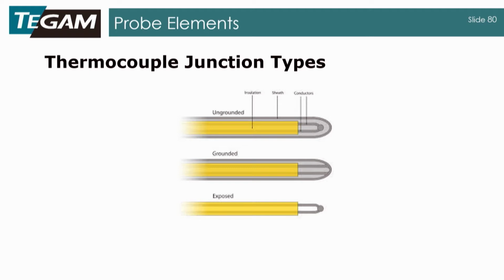Next is the grounded type. It's pretty much the same setup, except right here you can see that your thermocouple junction is actually bonded to the sheath. And then lastly, you have an exposed. And this is usually used for an air or gas measurement, and the obvious difference here is that there is no sheath, and you're just relying on the insulation and the thermocouple junction. This is going to have a much faster response time because you're only dealing with a small amount of mass there.